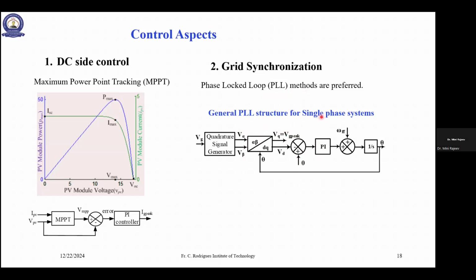But in single phase systems, there is a challenge because you need 90-degree phase shifted signals here. How to generate that 90-degree phase shifted signal is a challenge in single phase. In 3-phase, there is no issue like that, because there are already signals phase shifted by 120 degrees. But here you need to generate it. Based on that, the PLL methods are named, for example T/4. There are many methods; I am not going to detail them. Finally, what you get from here is sine theta, and that theta will depend upon the grid frequency.